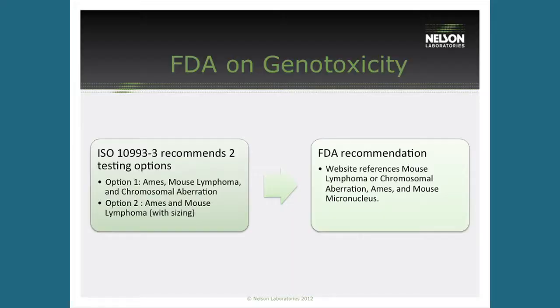So the FDA came out with their own guidance document. That guidance document says that you have to do the Ames test, then either the mouse lymphoma or the chromosome aberration — you choose between the other two in vitro tests — and then the FDA added the mouse micronucleus test, which is the animal test. Before in ISO 10993, the only time to do an animal test was as confirmation of a positive result in one of the in vitro tests. But the FDA is now requiring all medical devices to have the animal test run along with the Ames and either the mouse lymphoma or chromosome aberration.